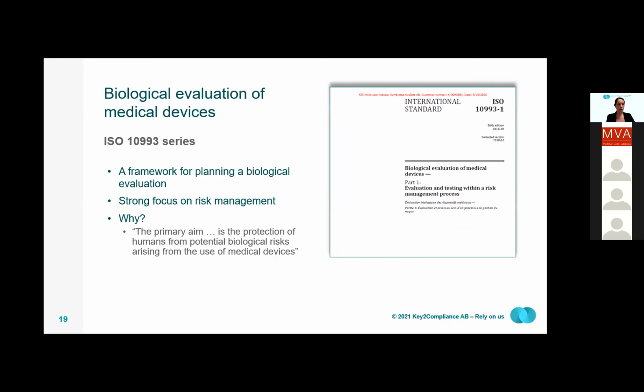So when talking about biological evaluations, you will inevitably talk about the ISO 10993 series. That's a series of standards containing approximately 20 parts, where the first part is the framework for how to plan and conduct a biological evaluation, and the other parts are essentially the different tests that you can perform. There is a strong focus on risk management, and the purpose of the entire standard series is the protection of humans from potential biological risks arising from the use of medical devices.